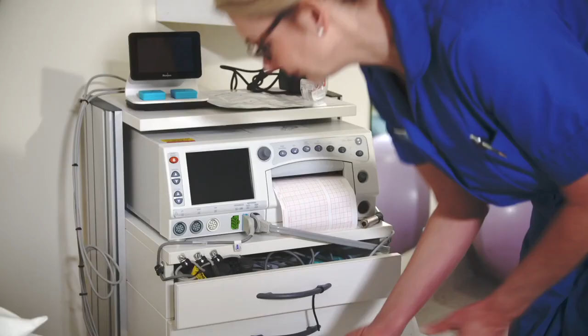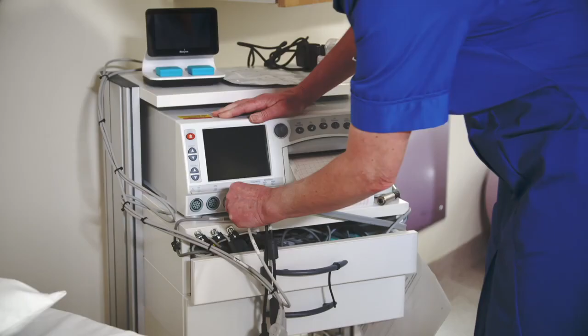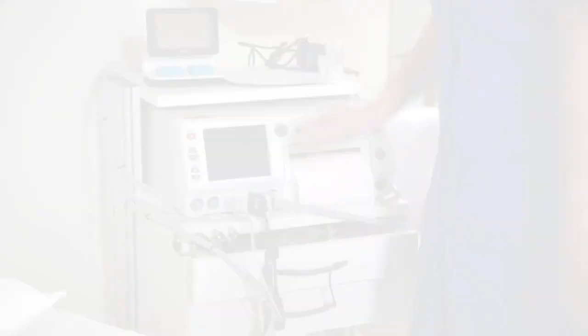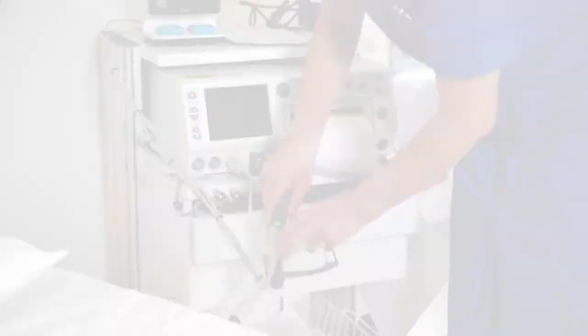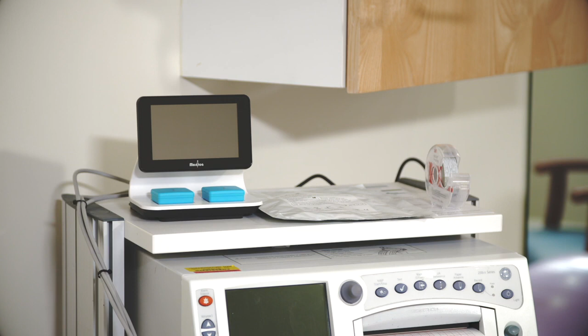Connect the Y adapter into the monitor. The 3 interface cables have color-coded plugs. The white plug connects to the Toco input. The green and gray plugs connect to the maternal ECG and fetal ECG inputs on the Y adapter. Now connect Novii to the AC power outlet. The Novii does not have an on-off switch, so after a few seconds, you will see the Novii start screen.